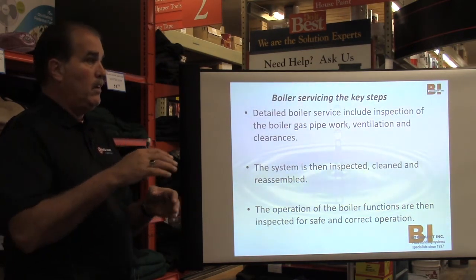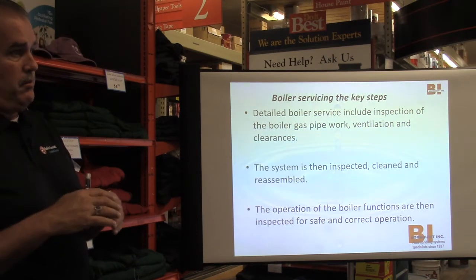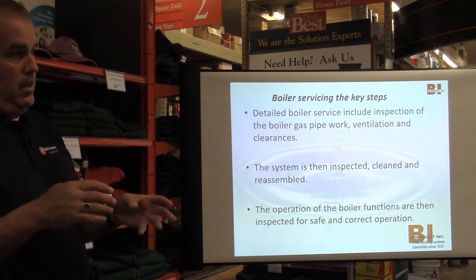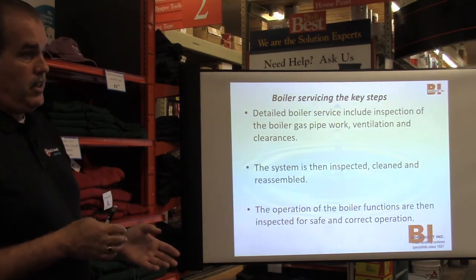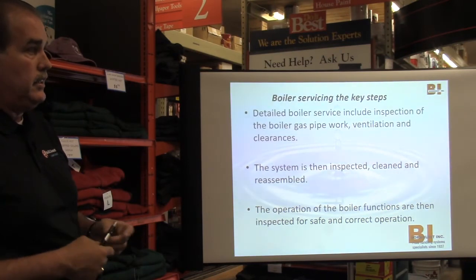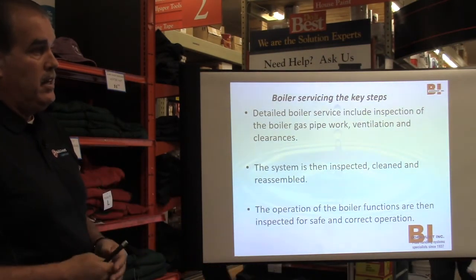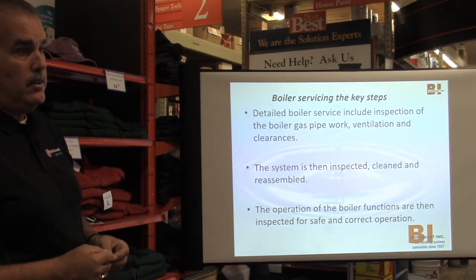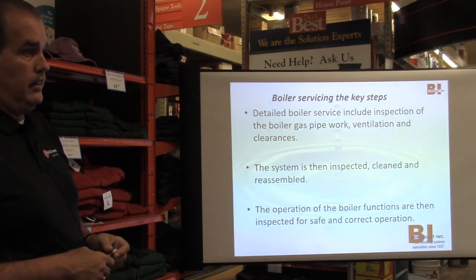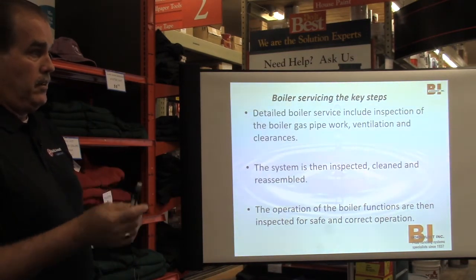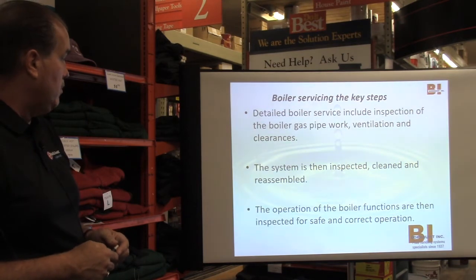because it's hard to do. You don't want to drain down the system. You're really going to create more problems. The outside, though, the heat exchanger side, typically they can clean because it gets sooted up and whatnot because it's exposed to the flue gas. So there you want that to get cleaned because that'll help the heat transfer and it'll help the emissions on the boiler.